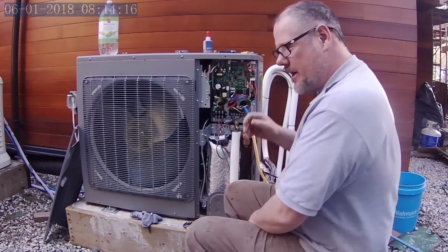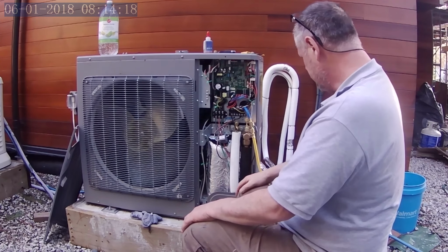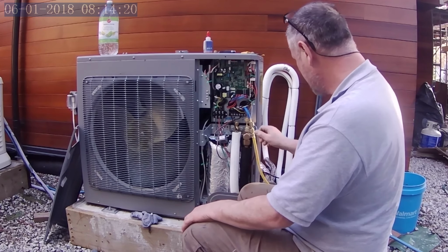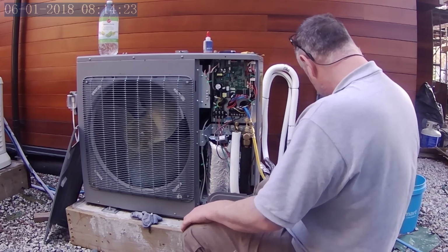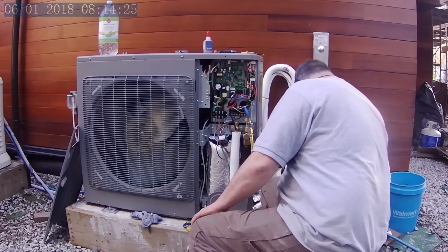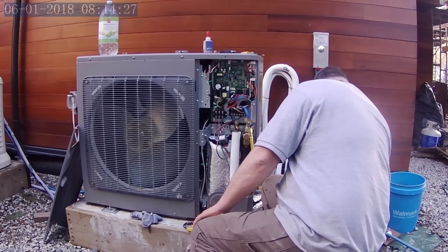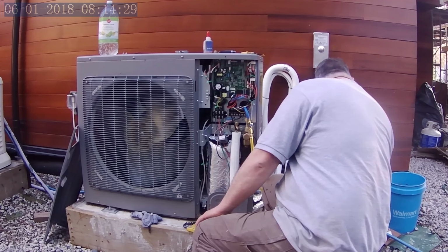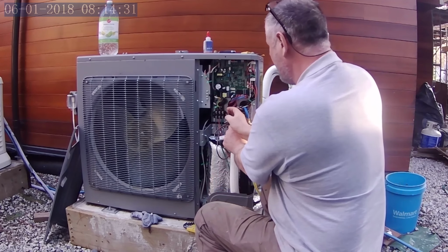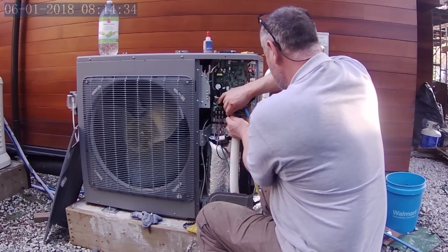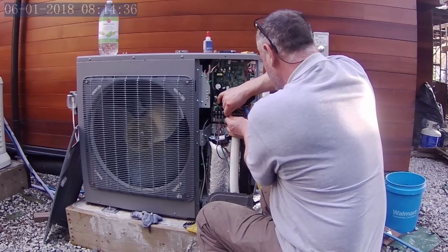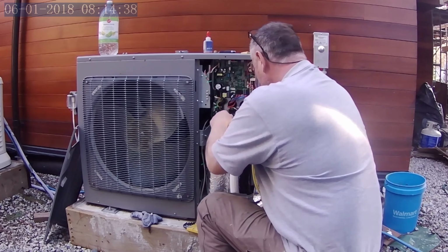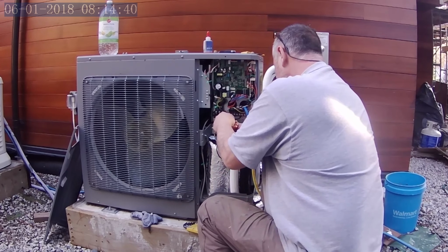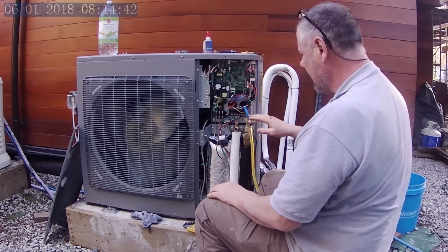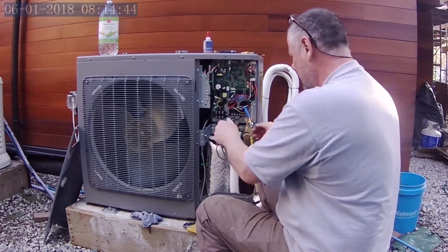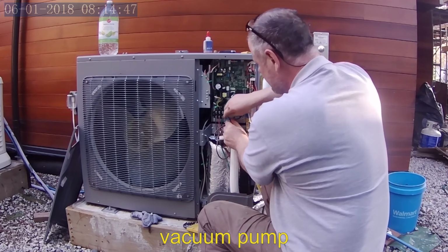Okay, we've had this on a few moments. Now we're going to isolate it and shut it off, and slowly crack open the liquid line on the heat pump, and we'll be able to hear the refrigerant releasing. And it's important to isolate it. You don't want the refrigerant going into the pump. You'll wreck the pump. So I have it.